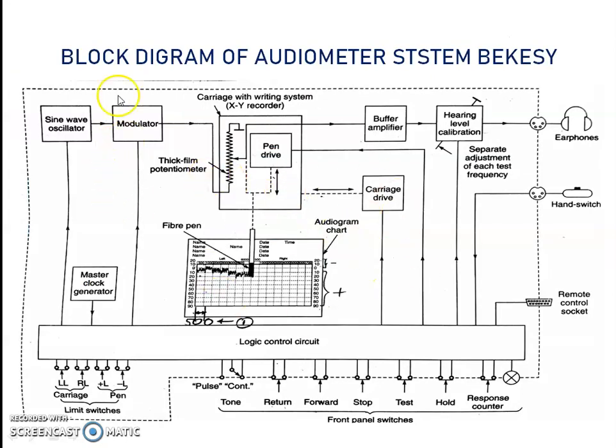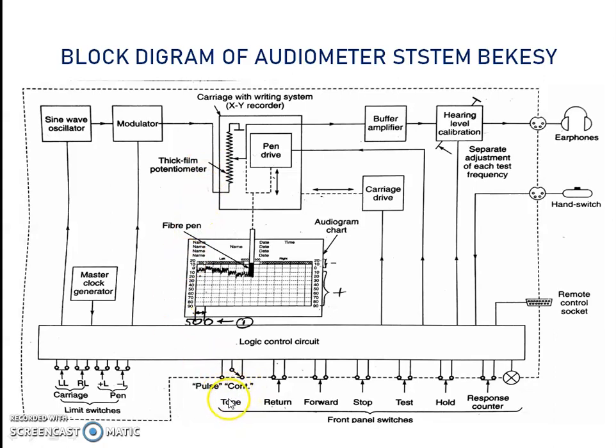Now we will discuss how this audiometer works. The sine wave oscillator generates the test signal in the range of 125 Hz to 8000 Hz. The test signal is first provided to the left ear and then the right ear. From the oscillator, the signal is fed to the modulator where the mode of operation is selected via a tone switch. Two modes are available: pulse and continuous.